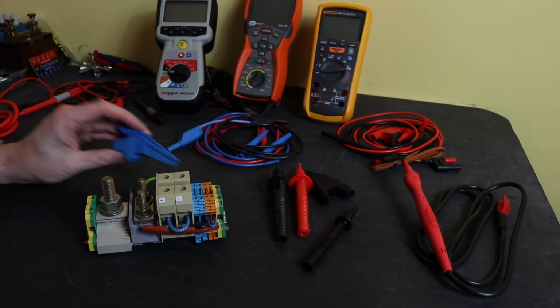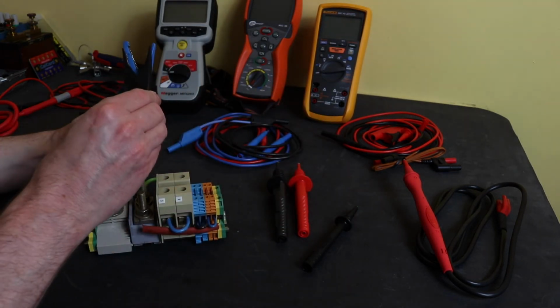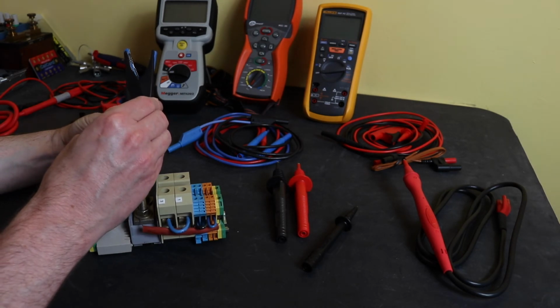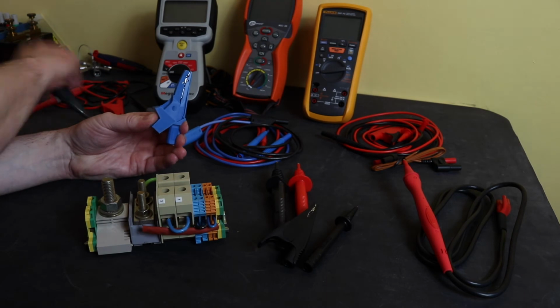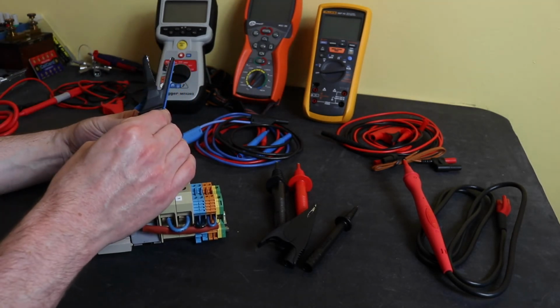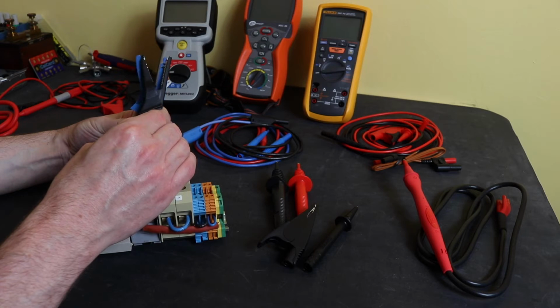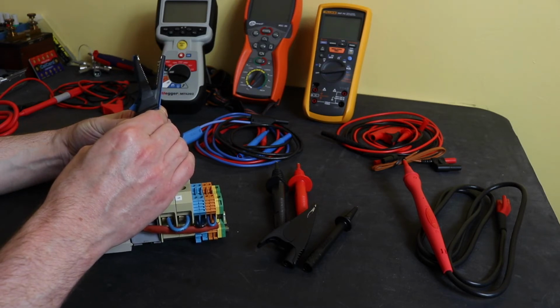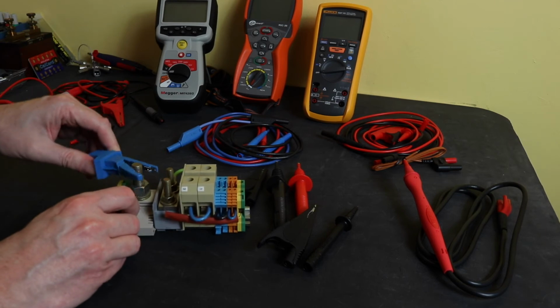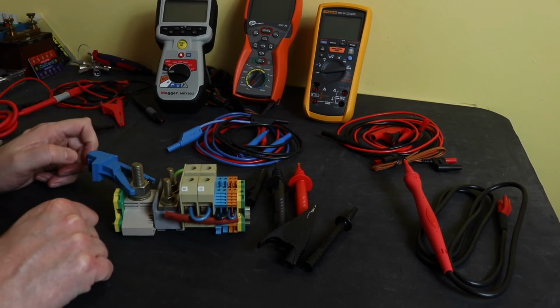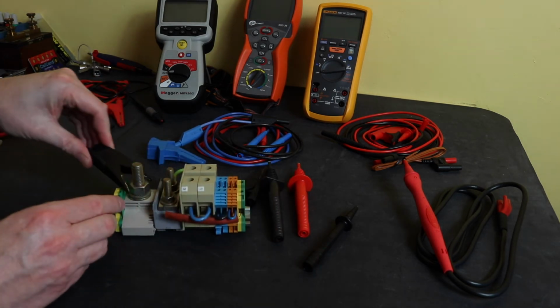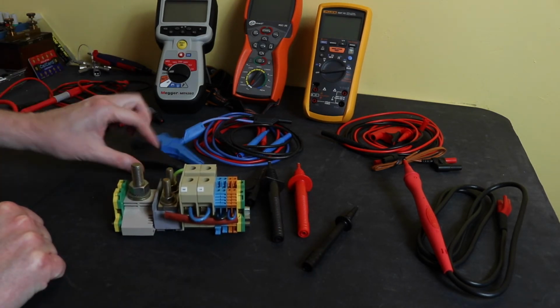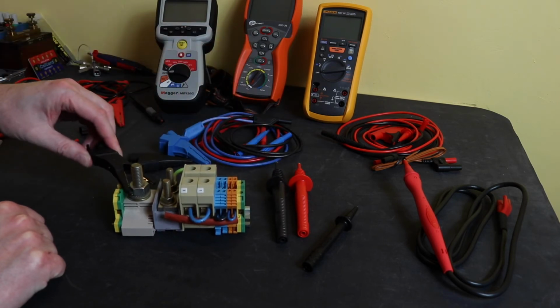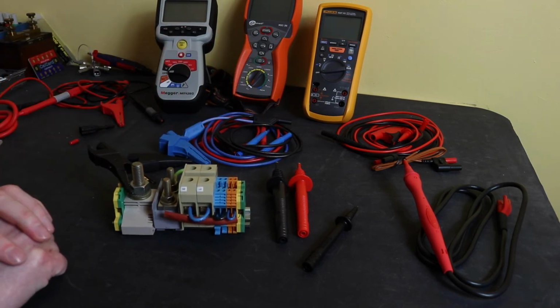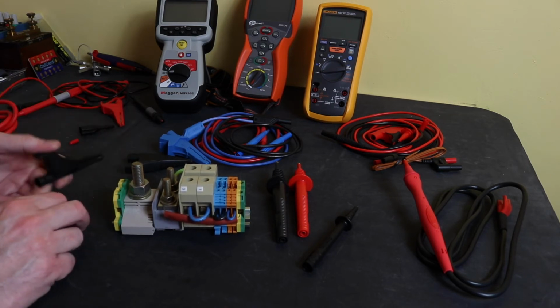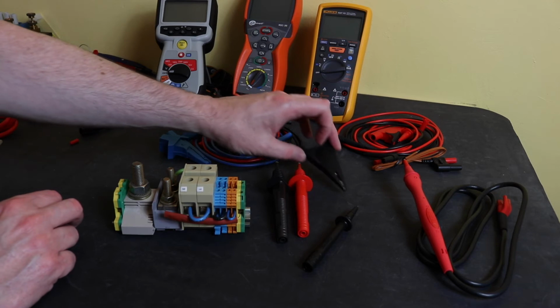In terms of their jaw capacity, the Sonel is pretty much the same as the Fluke, slightly bigger than the Megger. There's not an awful lot in it. They do quite happily go around a 12 stud, the M12, no problems. The Fluke does as well. And the Megger, you're kind of hitting the limit on the M12 nut there, but it does go around. They are perfectly usable in that respect.